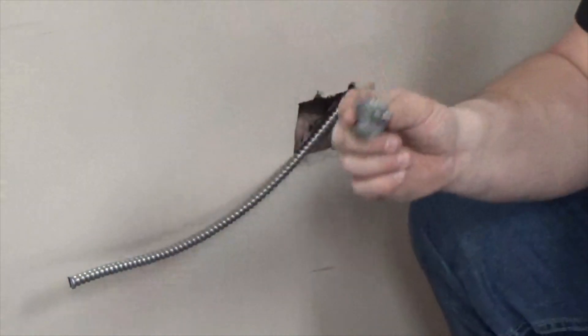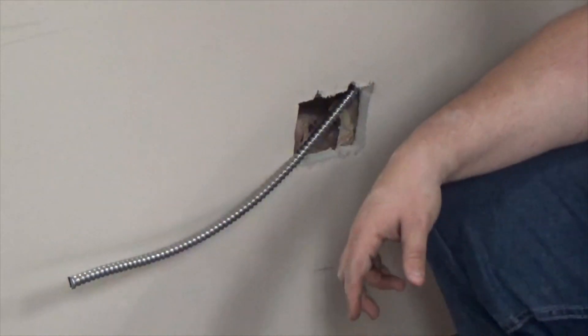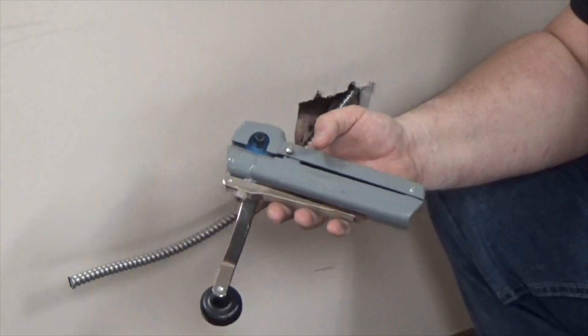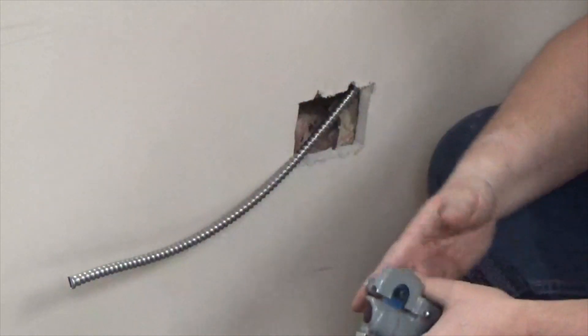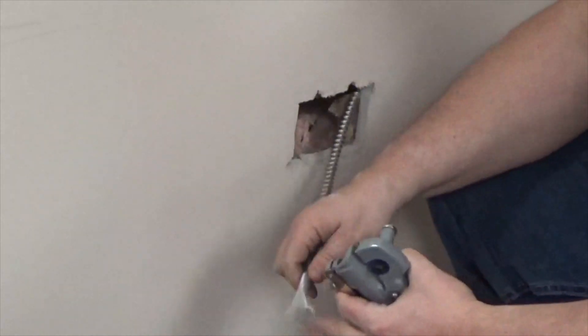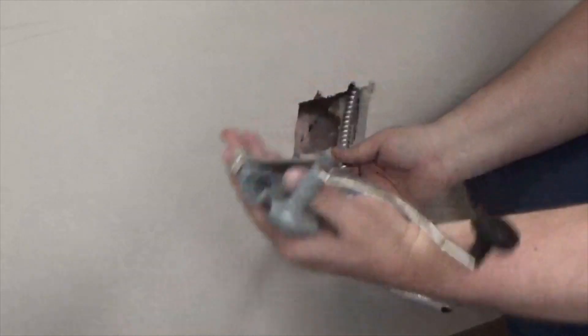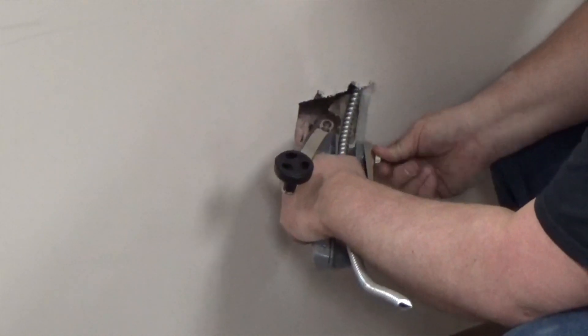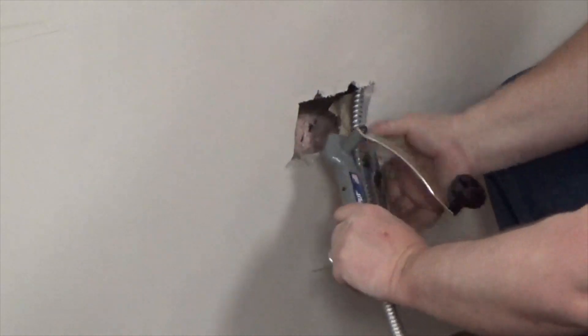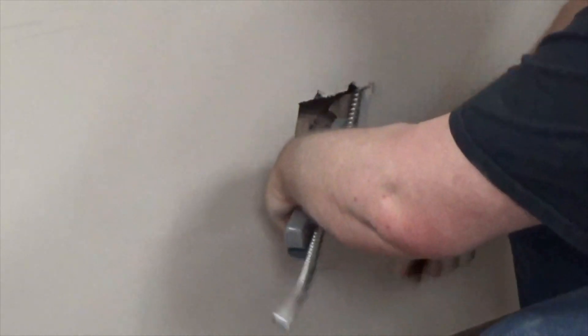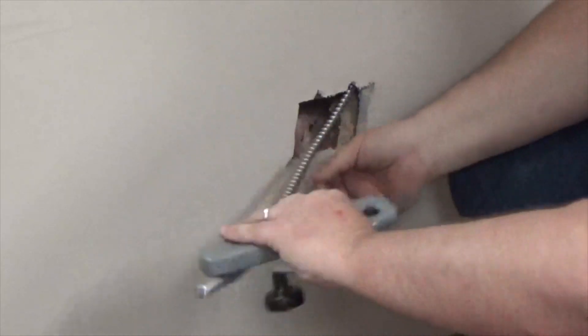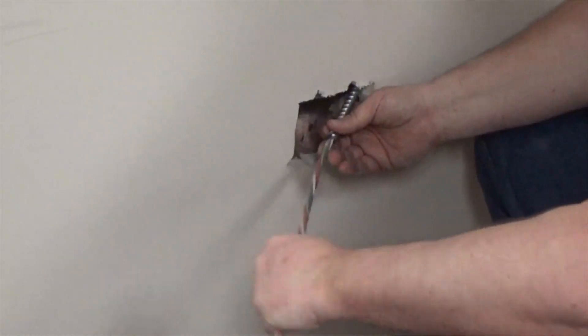So in order to do this correctly, we have to install a connector. So I'm going to use my Greenlee RotoSplit that you can purchase at any hardware store or electrical supply house. Now I am going to need to have a good amount of cable here. So what I'm going to do is I'm going to take my RotoSplit. And I'm going to set it so that I can cut it where I need it to be. I'm going to squeeze it. Give it a couple cranks. Two, three. And you'll feel it kind of cut through. You don't want it to go too deep. If it goes too deep and it cuts your conductor, then that's a bad thing. Take it right off.